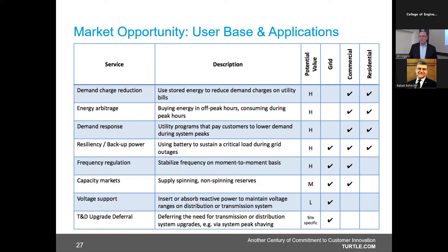Energy arbitrage is the second one. If rates differ at different times of day, you can store power in the battery when it's low cost, and discharge it when grid power is expensive. This is a big issue in California and Hawaii. Base rate might be 10 to 15 cents a kilowatt hour, but you could pay over 70 cents at certain times of day. So the rates click up quite a bit.